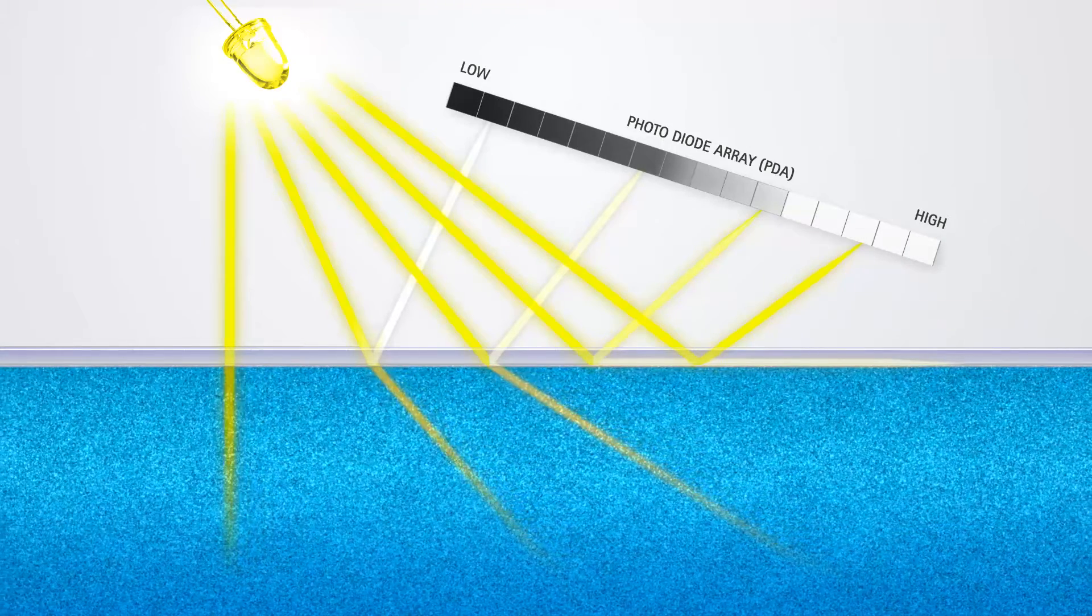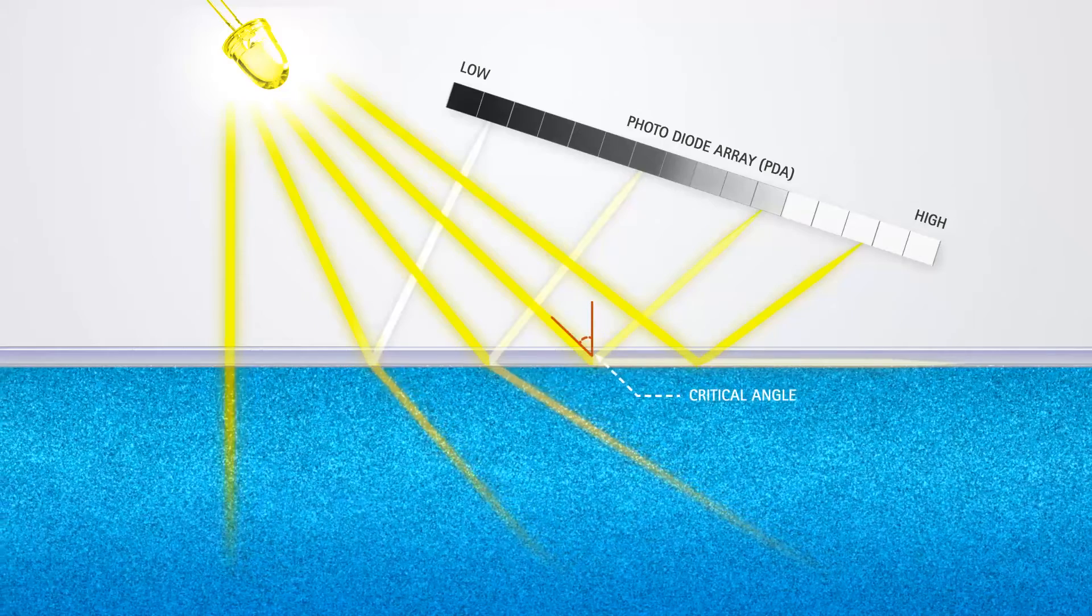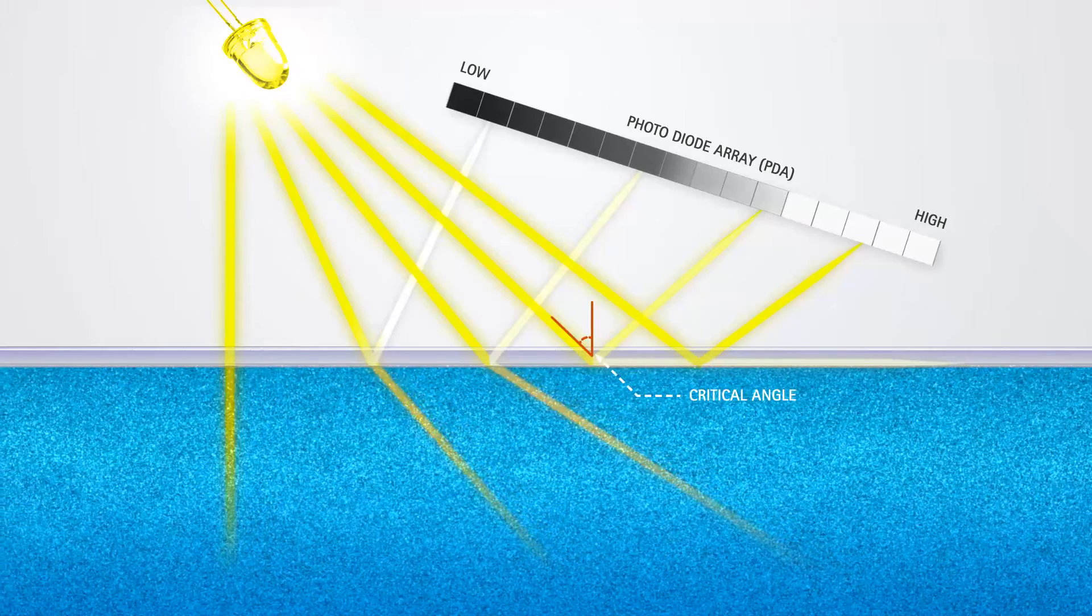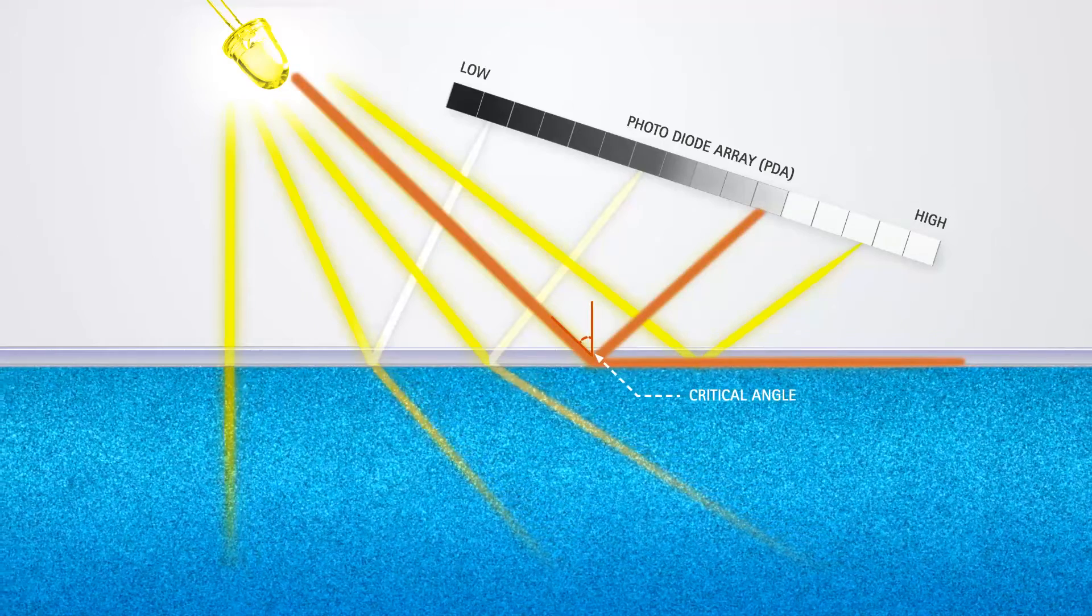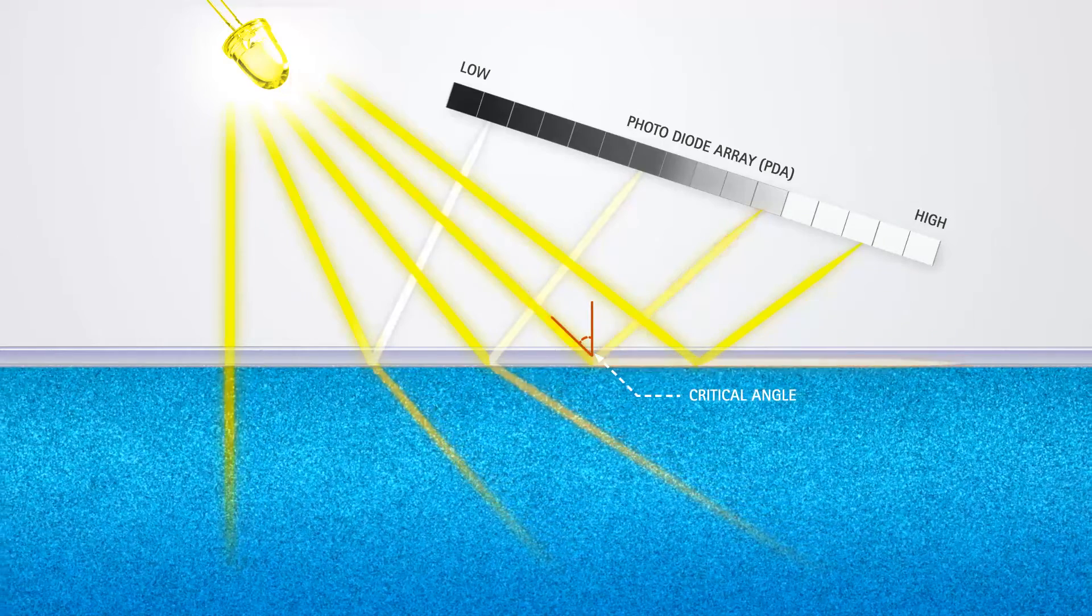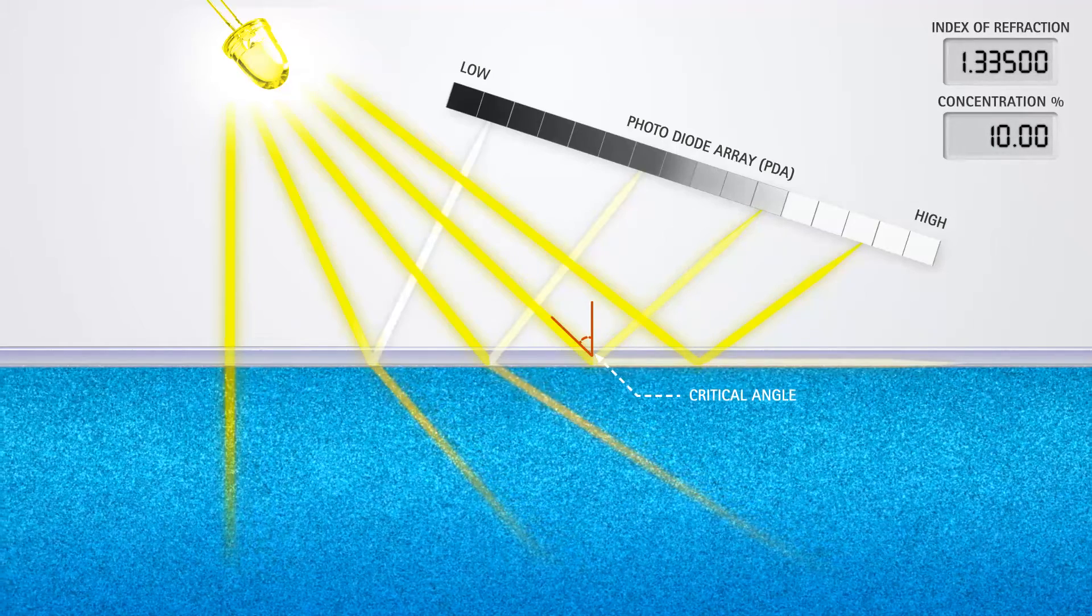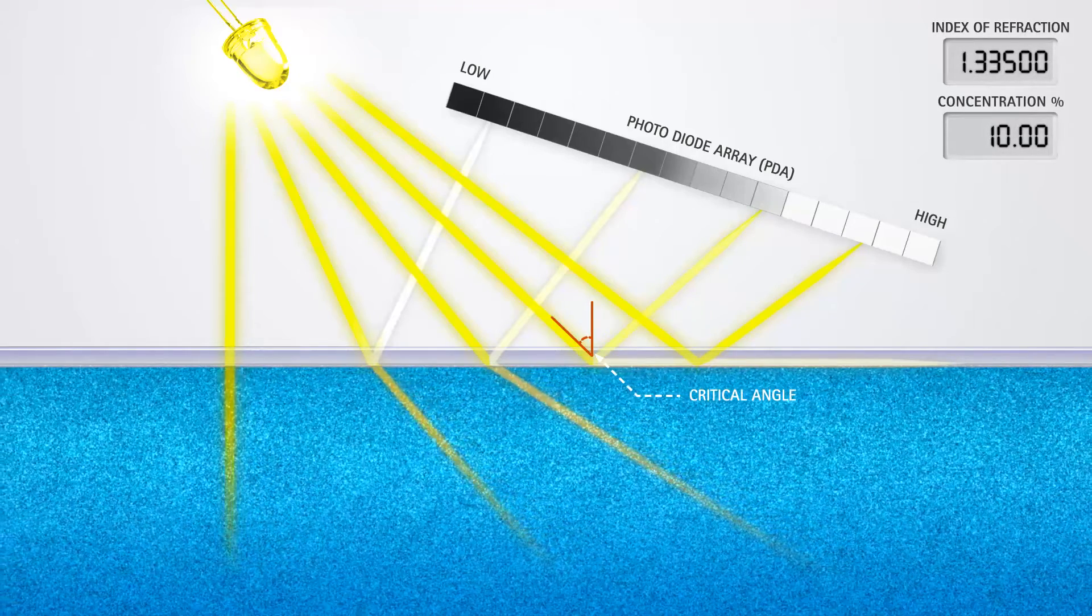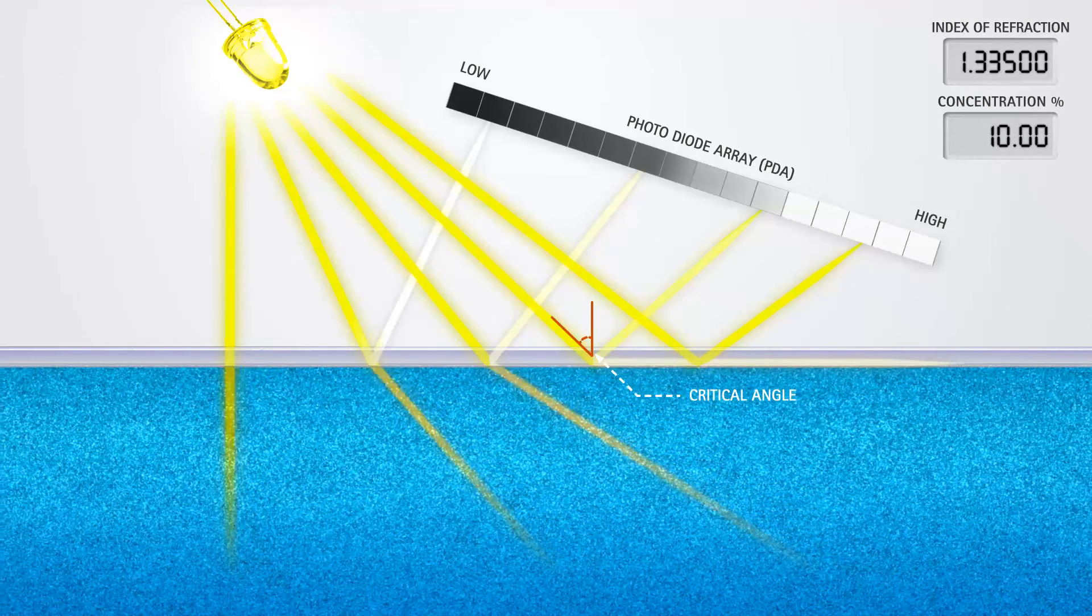At a critical angle, the light no longer refracts into the liquid, but completely reflects back to the PDA. The Index of Refraction is calculated from the critical angle, using Snell's Law.